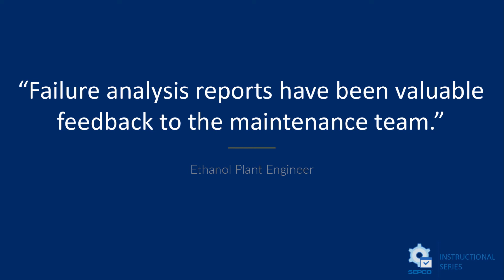And going back and following up with this engineer, we wanted to look at other things, see what he needed from us, and get some statements on what he thought was different about what we were doing compared to the other seal suppliers or manufacturers that had been in this plant in the past. A couple of the statements we got from him: one was the failure analysis reports had been valuable feedback to the maintenance team. We thoroughly discussed these reports. They're very detailed. Every component of the seal was broken down, inspected, measured, and a full detailed report is supplied to these plants so they can see exactly what we see.